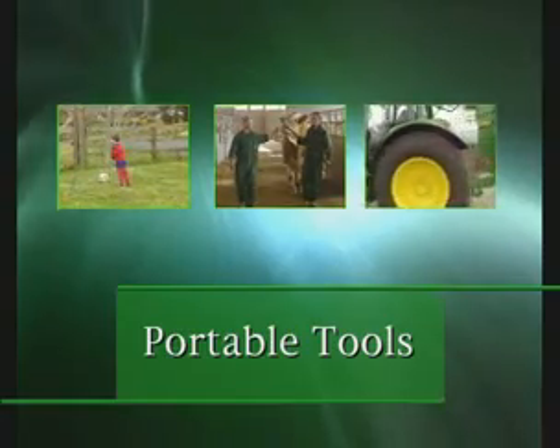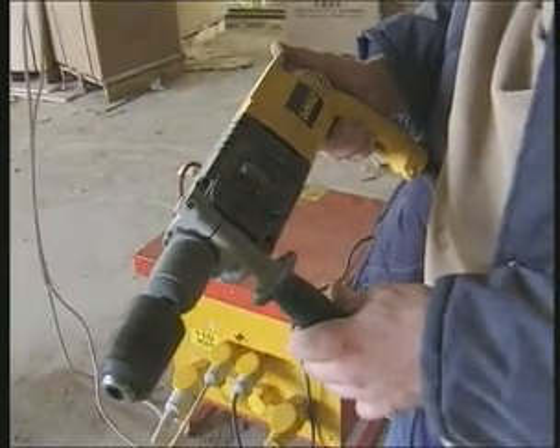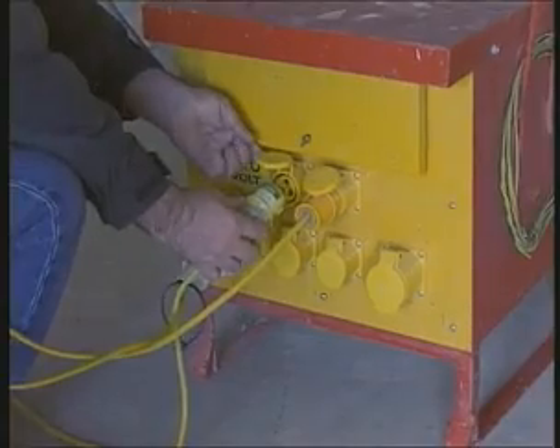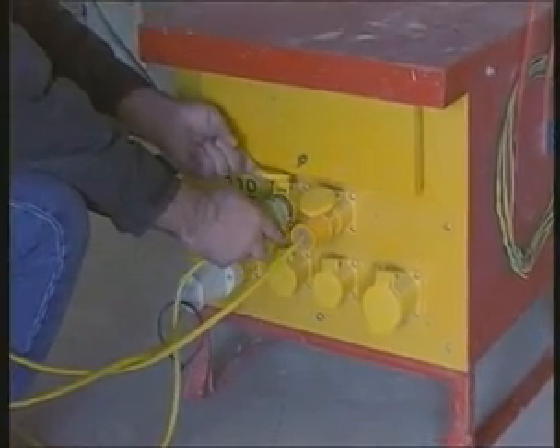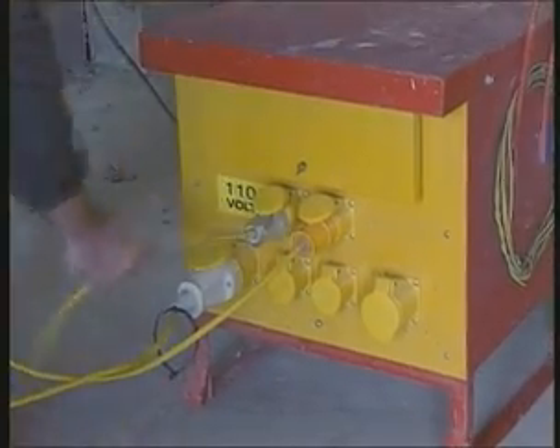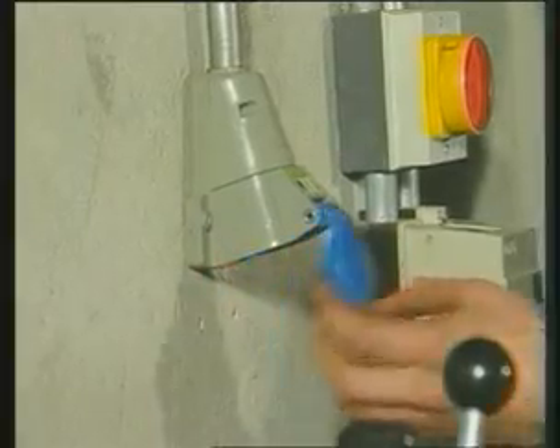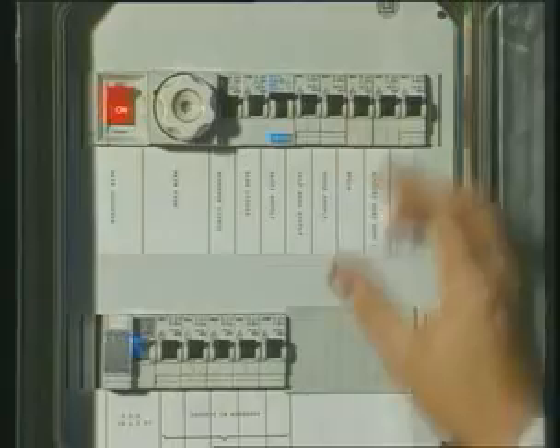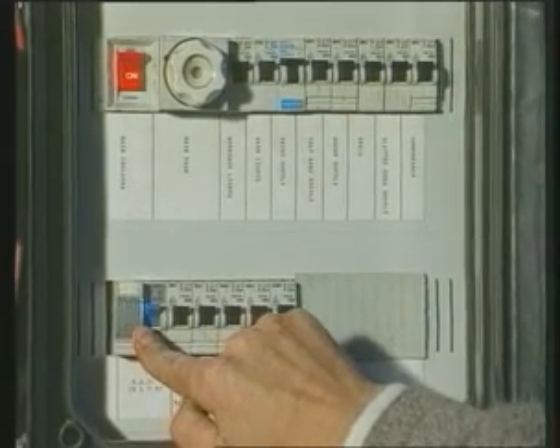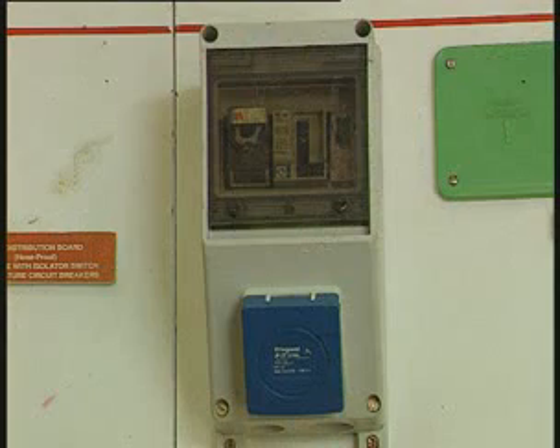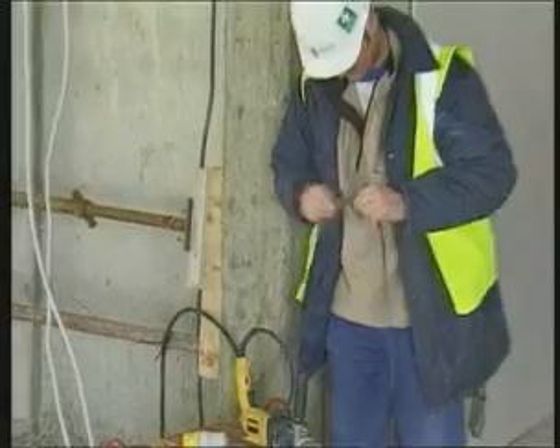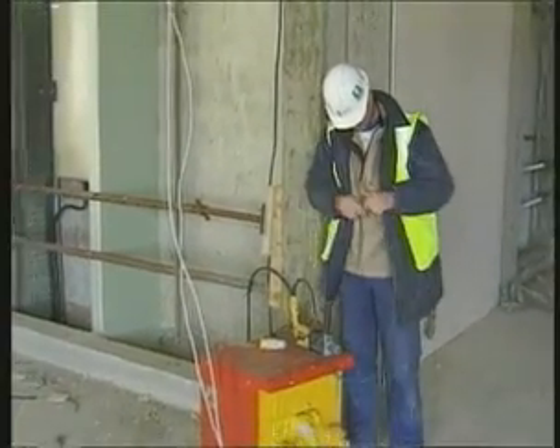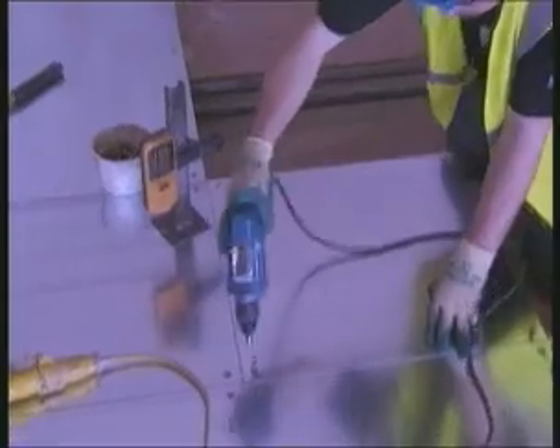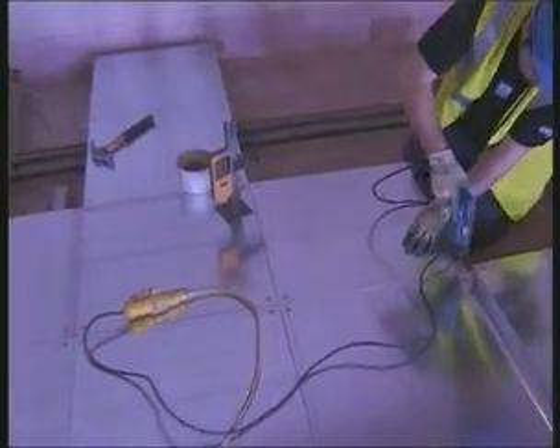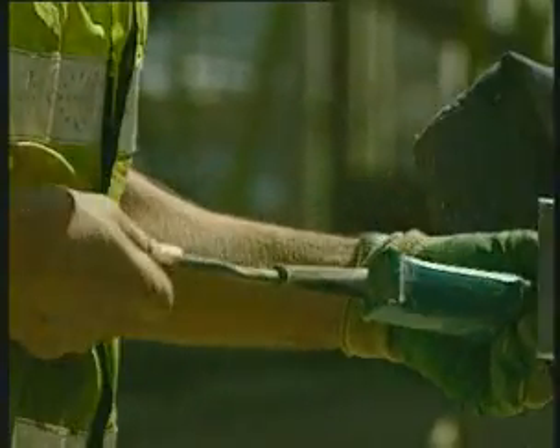Portable tools. Low voltage equipment operating at 110 volts from a transformer is to be recommended in more onerous conditions. If it's not possible to operate equipment at reduced voltage, it should be used through appropriate sockets, which are protected by means of 30 mA RCDs. Before using any portable equipment, it should be carefully inspected for any damage. Particular attention should be paid to the flexes and any worn or damaged ones replaced before use.